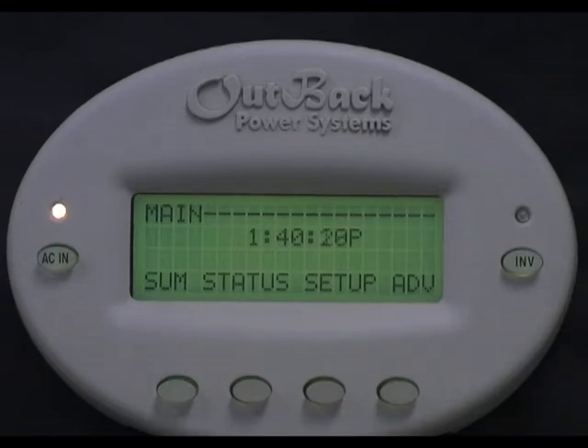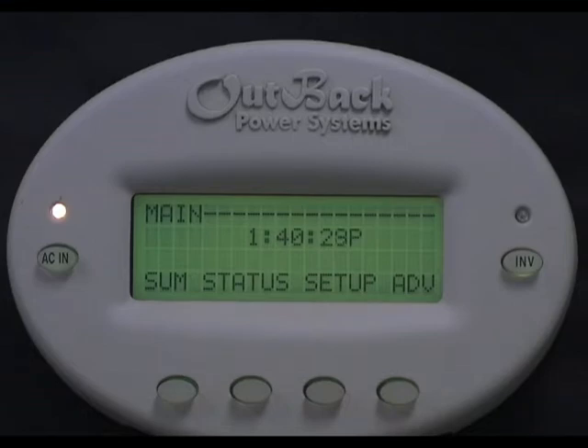We can tweak certain settings within the AGS programming to fit your needs. Keep in mind if you don't change any of these settings, all but volt start will be disabled. Let's start with Quiet Time. Quiet time is when you don't want the generator to run — for instance, 2 in the morning. This will only be overridden by the 2-minute volt start if the voltage hits the 2-minute volt start parameter.